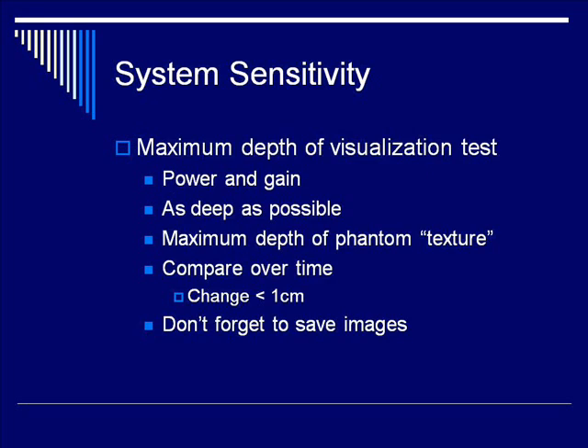The test we use when looking at a phantom for system sensitivity is called the maximum depth of visualization test. You optimize power and gain, set the depth to as deep as possible, and find the deepest place where you can still see the tissue-like texture in the phantom. You compare this number — how deep that is — over time. A change of more than a centimeter is really concerning. Remember to save the images so they can be compared.